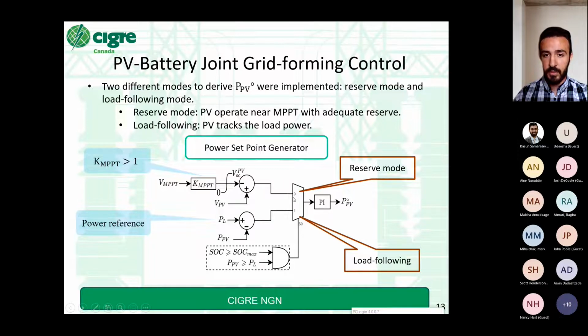Looking at the reserve mode control diagram, we can see that the power set point is derived by the VMPPT and the VVPV that is multiplied by a coefficient, which should always be higher than one. It's higher than one because in reserve, we need to operate the PV array between the MPPT point and the open circuit voltage point.